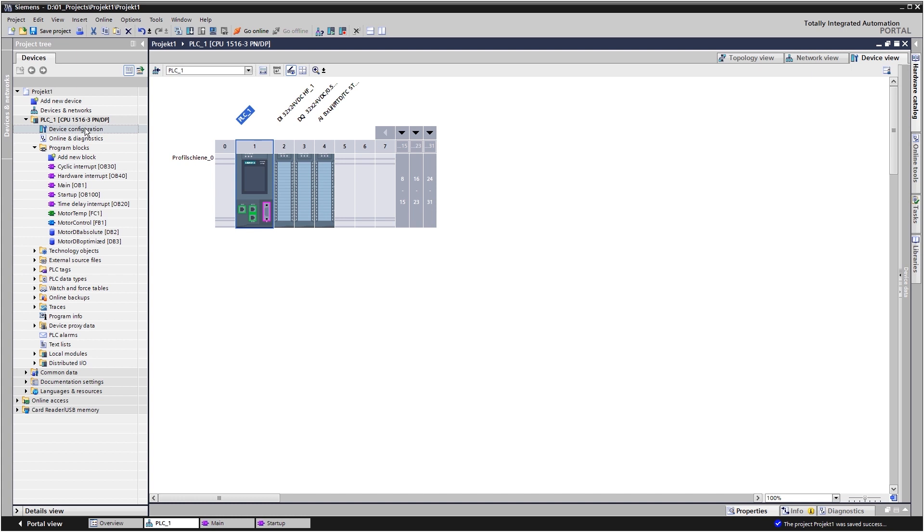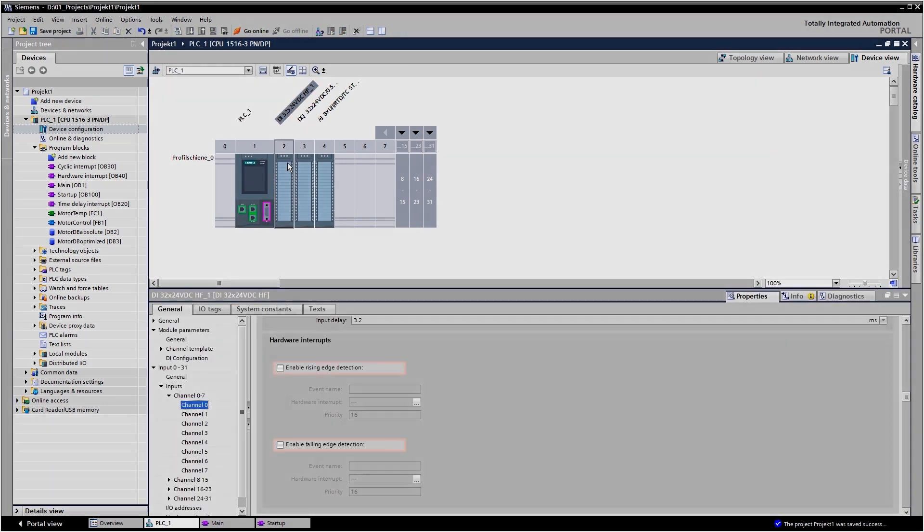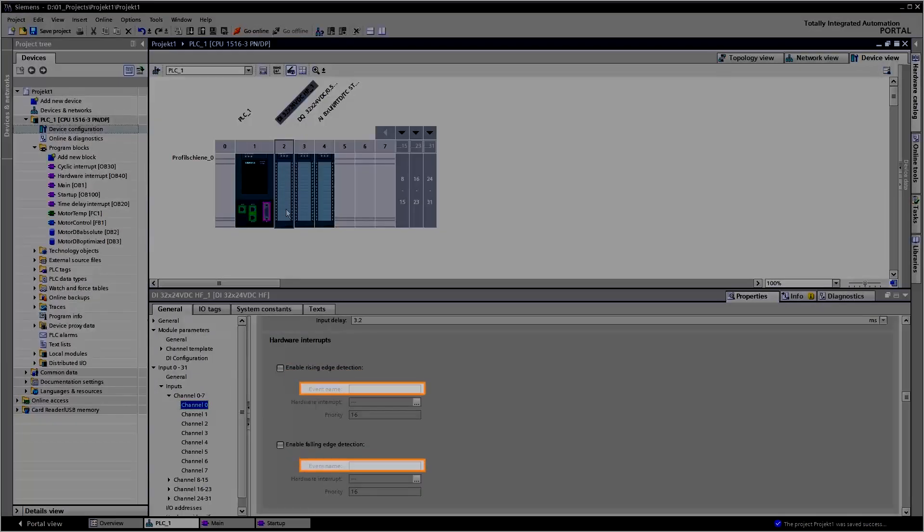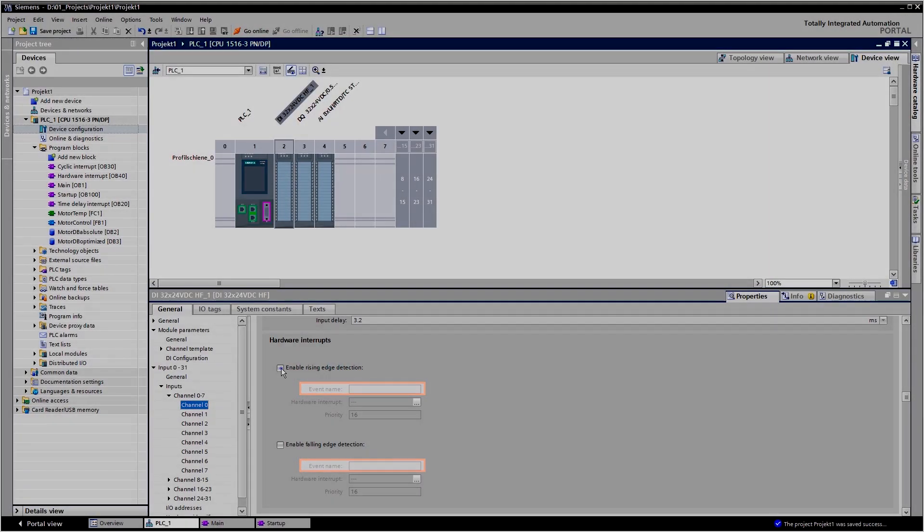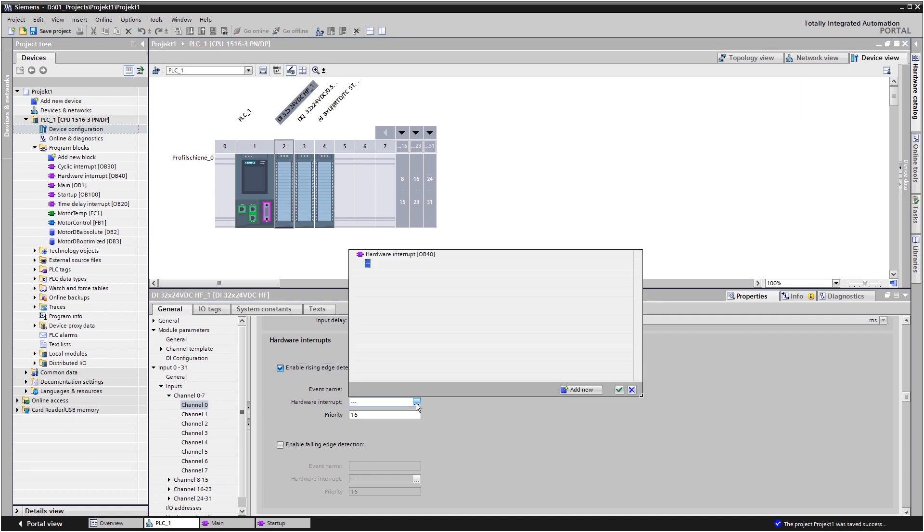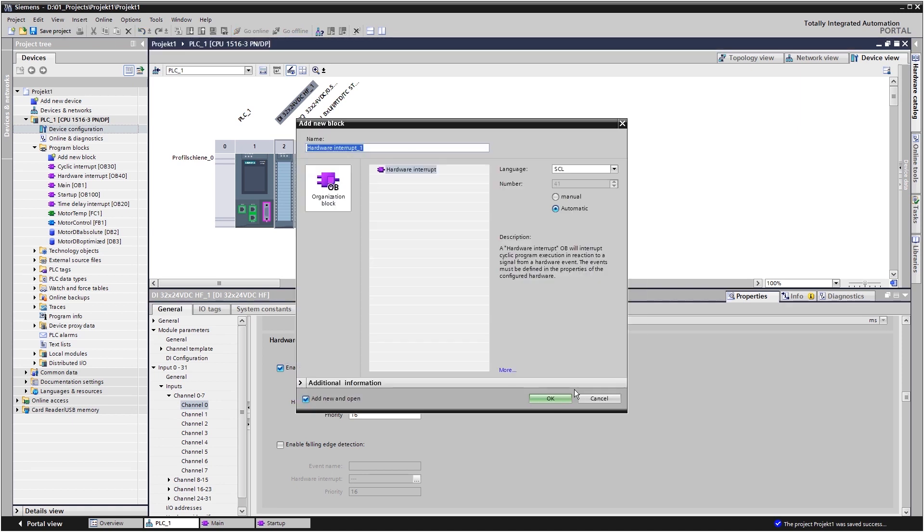This OB will monitor a specific signal connected to a module regardless of the cycle of the main OB. As a first step, you specify the condition or the event that should trigger the alarm. Now you can assign this event to an existing process alarm OB or create a new one.